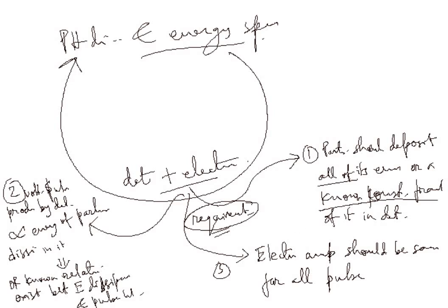Okay. Now, what about charged particles? Well, charged particles deposit all of their energy in the detector as long as their range is shorter than the size of the detector. Whereas gamma rays do not necessarily deposit all of their energy in the detector regardless of the detector size. This is why, you know, the exponential Lambert law, I equals I0 e to the power minus mu x. This gamma attenuation relation, you know. What does this mean? This means that there will always be a probability for a gamma ray escaping because of its exponential attenuation nature.